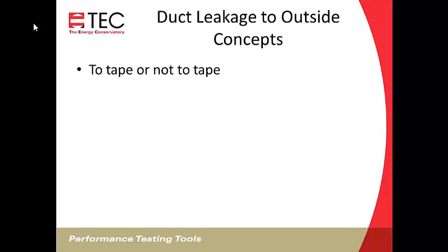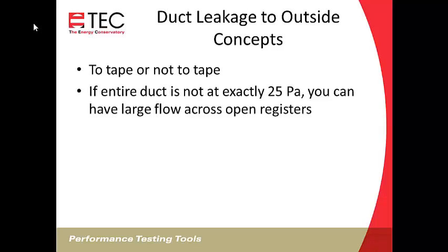One of the issues that comes up periodically is whether to tape or not tape the registers and grills during the duct leakage to outside test. If the entire duct system is not at exactly 25 pascals, you can get pretty large flows through open registers even with a small pressure difference. And we know that, especially with leaky ducts, we don't get even pressure distribution throughout the whole duct system. If you're near a large leak, it's likely to be at a different pressure than the rest of the duct system. So there are a number of reasons why it is important to tape the registers during that duct leakage test.